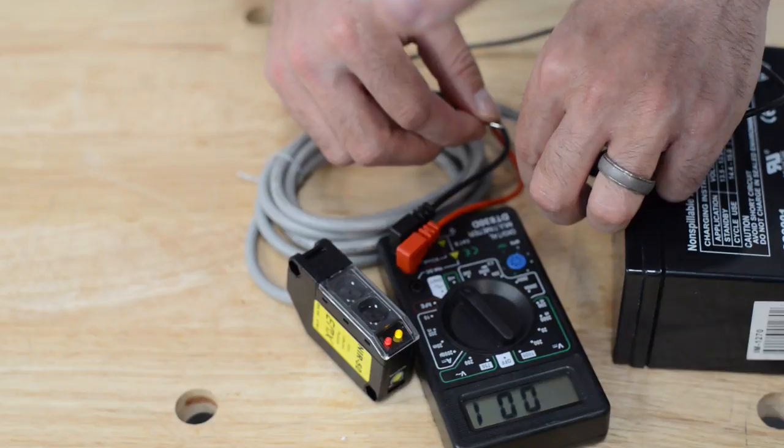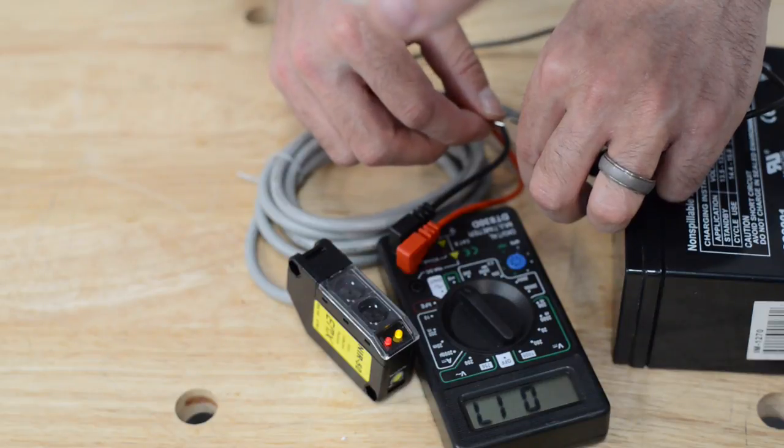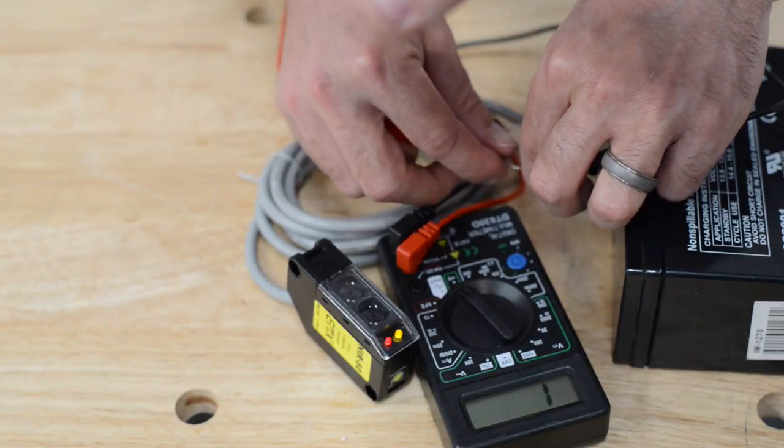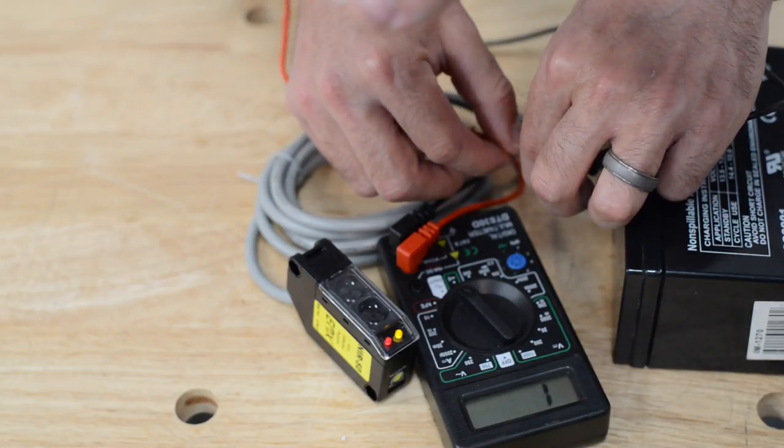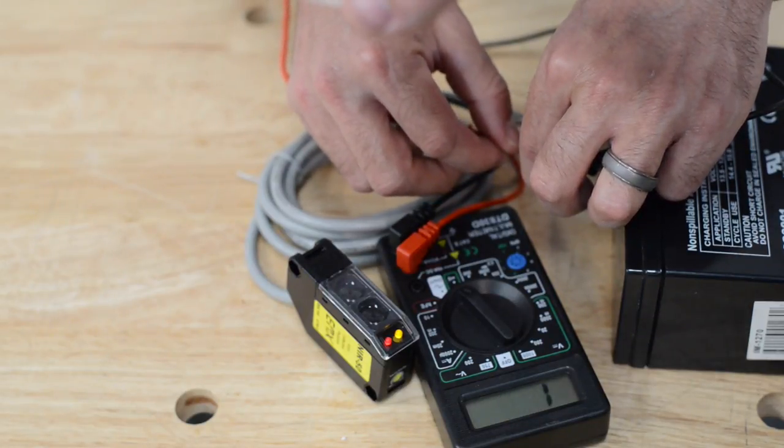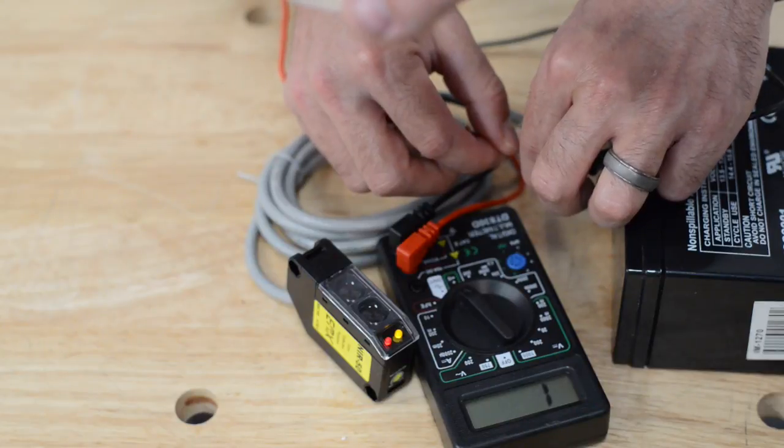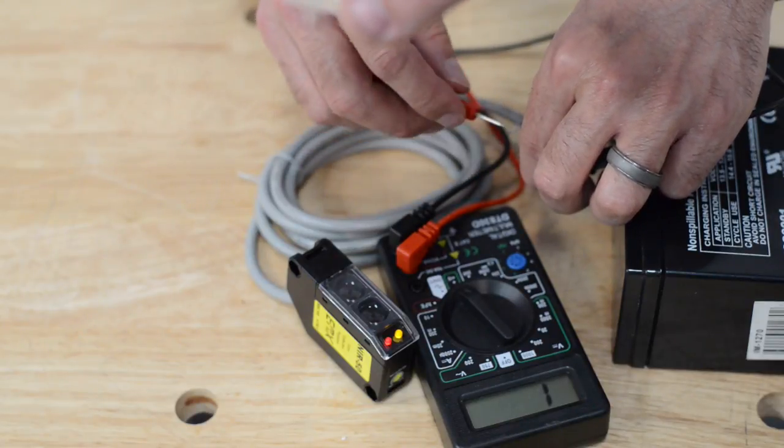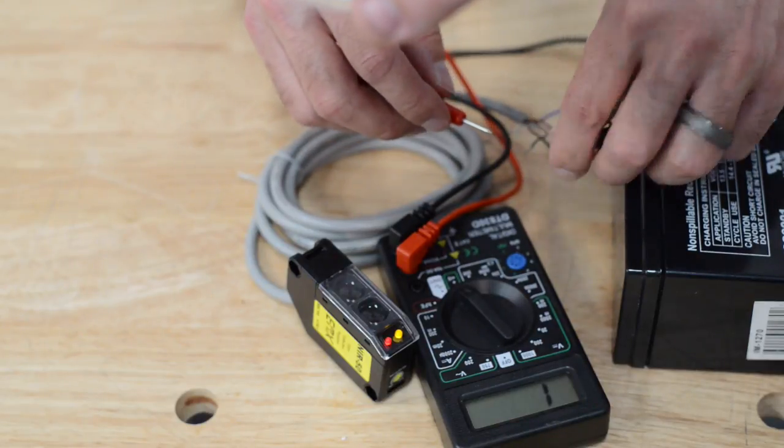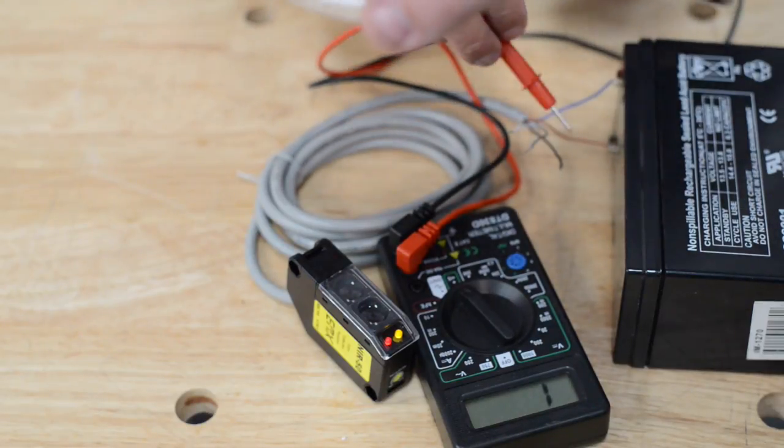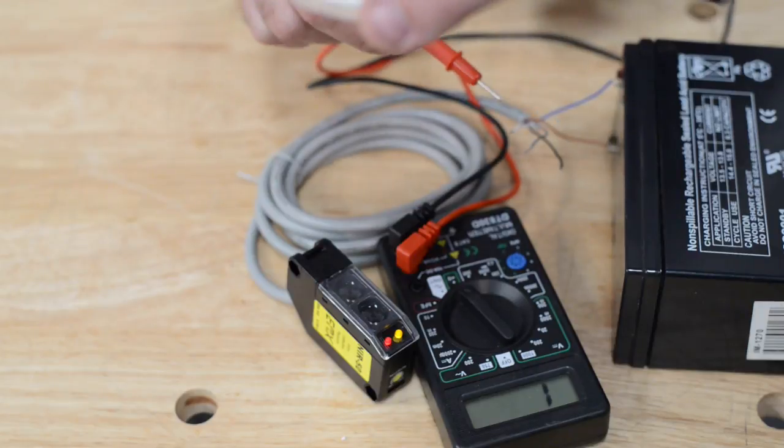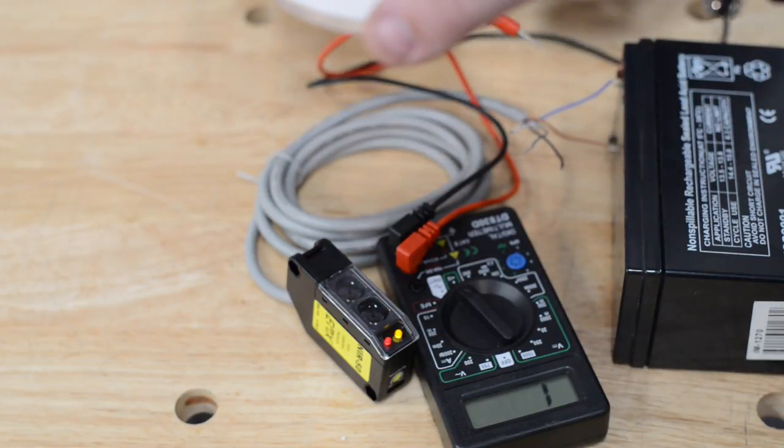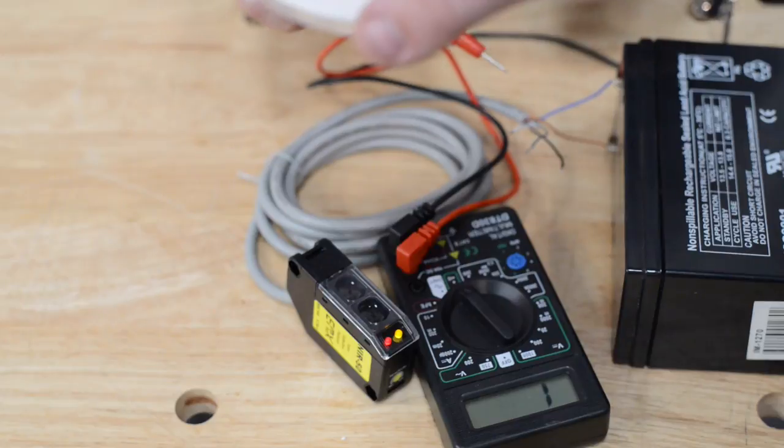So by process of elimination, I should be able to touch the black to the gray and not have continuity. Excellent. I do not. So I know the black is my normally closed. I know the white is the common and the gray is the normally open.